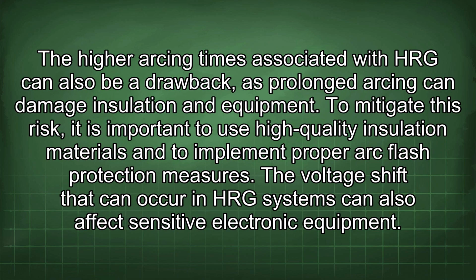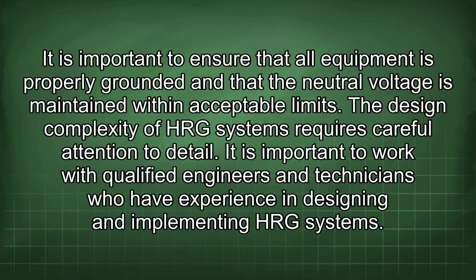The higher arcing times associated with HRG can also be a drawback, as prolonged arcing can damage insulation and equipment. To mitigate this risk, it is important to use high-quality insulation materials and to implement proper arc flash protection measures. The voltage shift that can occur in HRG systems can also affect sensitive electronic equipment. It is important to ensure that all equipment is properly grounded and that the neutral voltage is maintained within acceptable limits. The design complexity of HRG systems requires careful attention to detail.